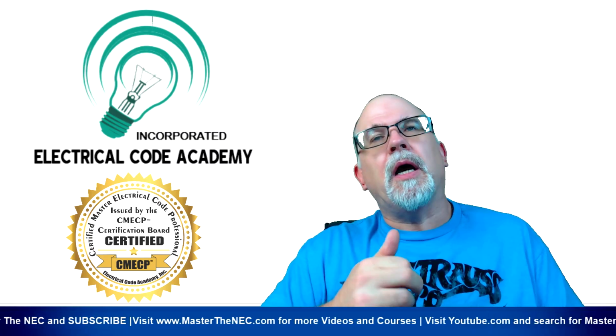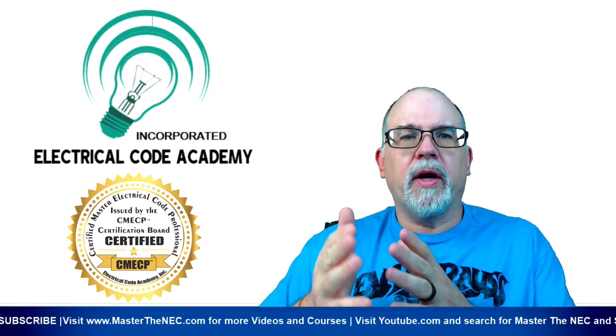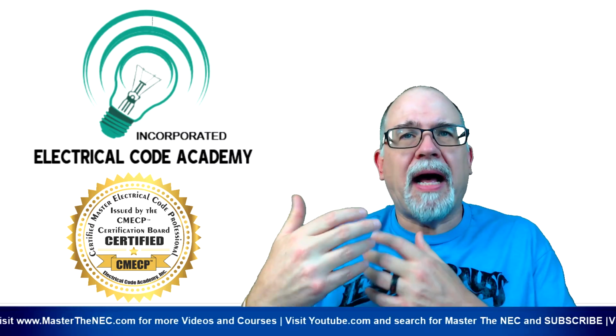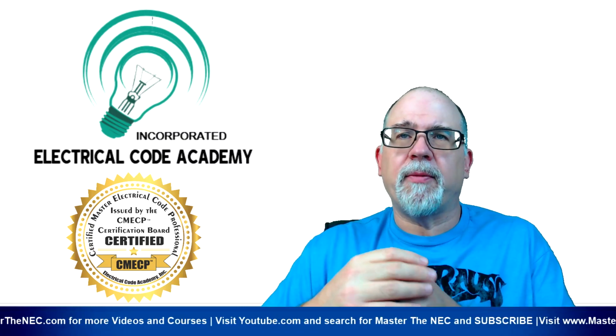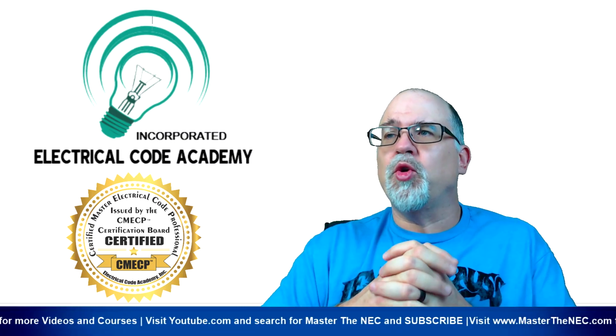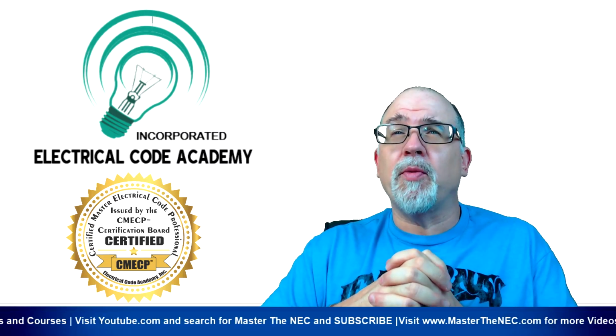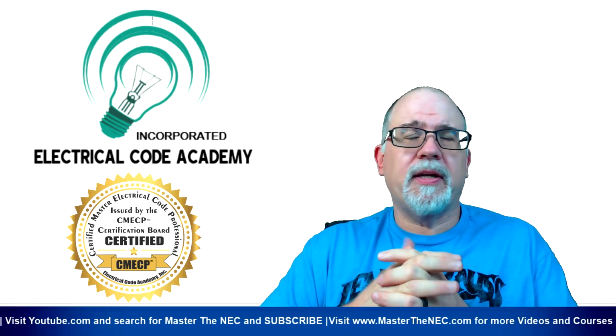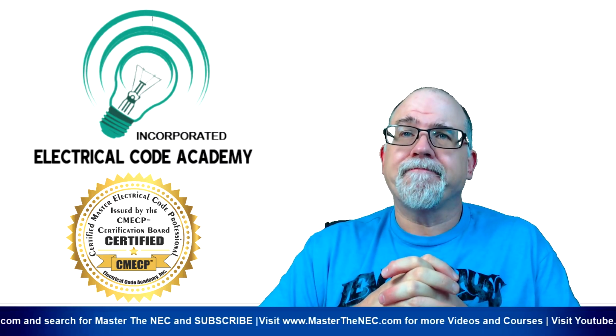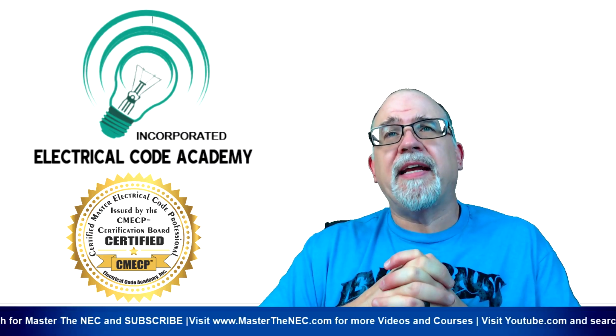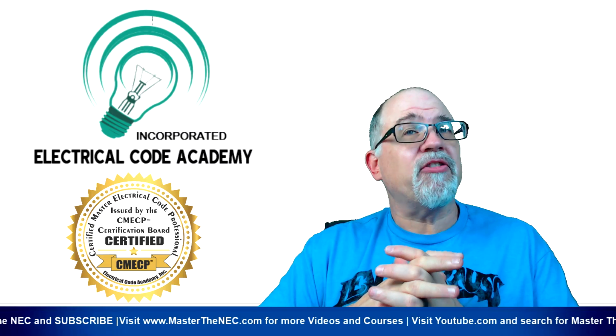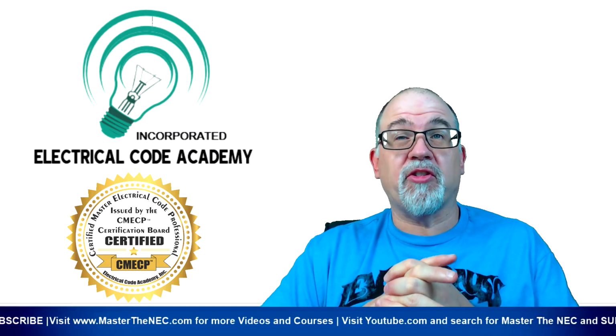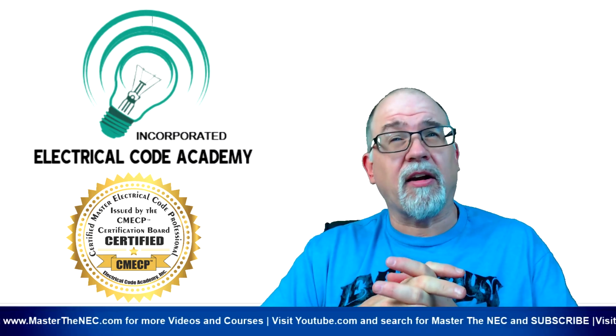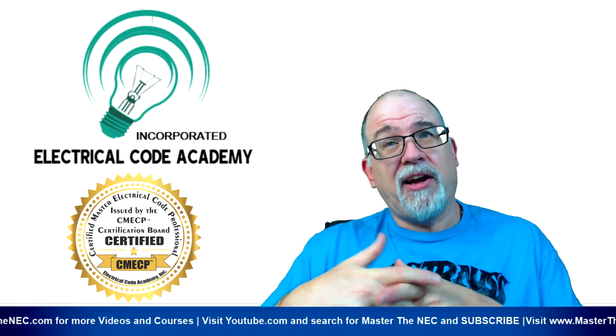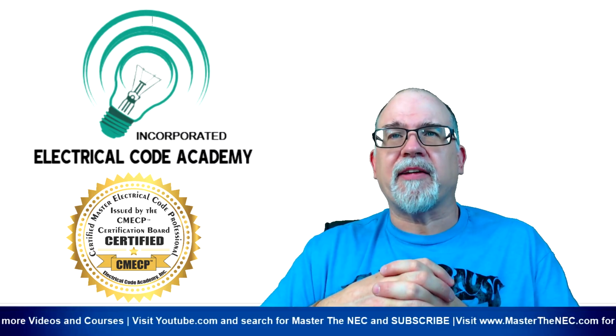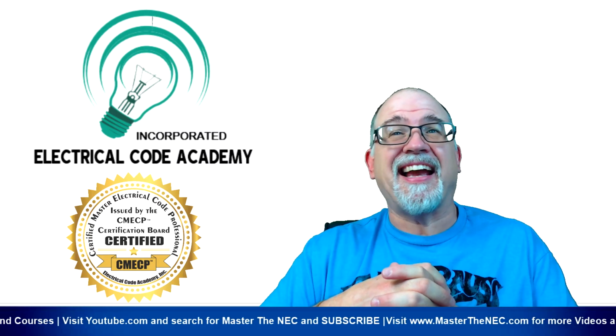So that's done there. And on the load side, again, we're dealing with the application where we're only bonding at that point. Okay, we're not using that FMC as an equipment grounded conductor. We're just bonding. If you want to loop it through and you think that that's going to help you in some way, go for it. If you want to put a bonding lock nut on it, have at it. It's totally up to you. But remember, we're dealing with circuits on the load side that are not service conductors. Okay, let's not get it confused: just because they're on the secondary side of a transformer doesn't mean they're service conductors. They are not. Okay, like we said, in our case, that primary side's only at 125%, the primary protection, so it theoretically could protect the secondary as well.